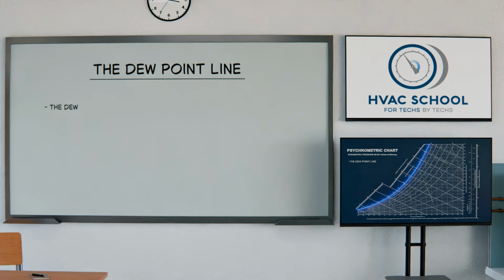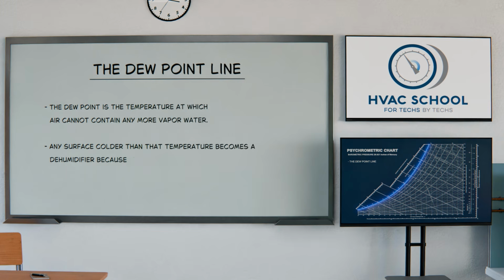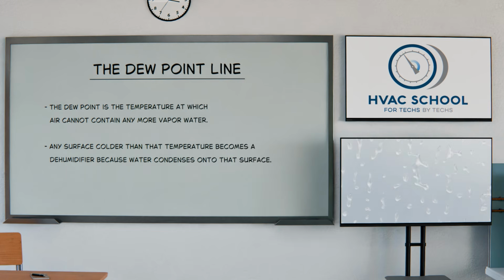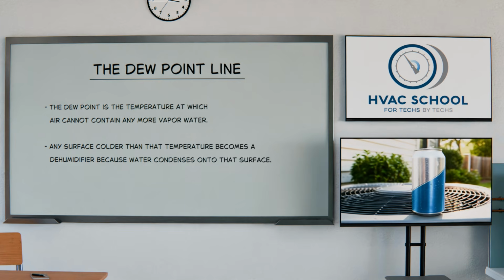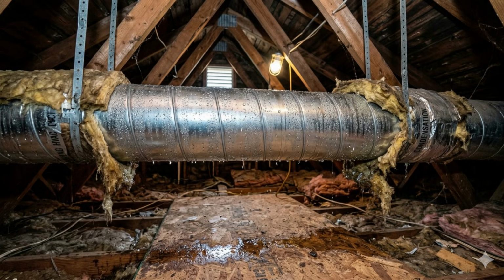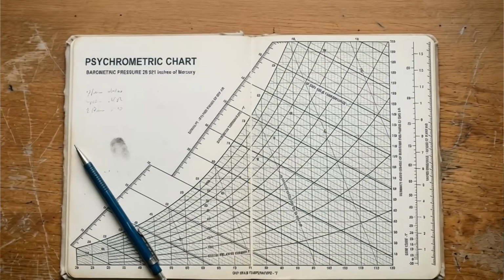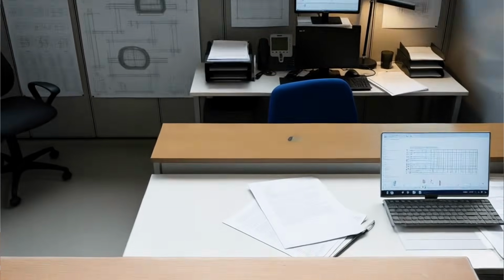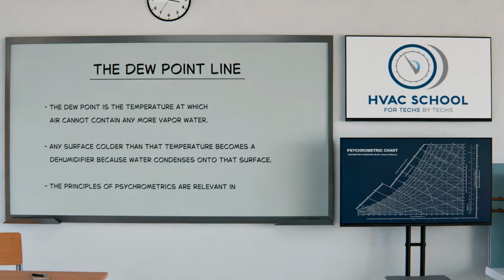The dew point is the temperature at which air can no longer contain any more water vapor. Any surface colder than that temperature becomes a dehumidifier because the water condenses onto that surface. That's why the beer can you use to calculate your superheat sweats on a humid day. And that's why attic ducts often drip. It's why psychrometrics isn't just for textbooks. It's for every service call we run, at least in humid climates.